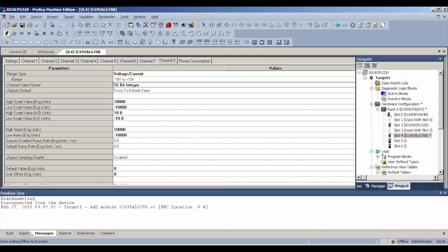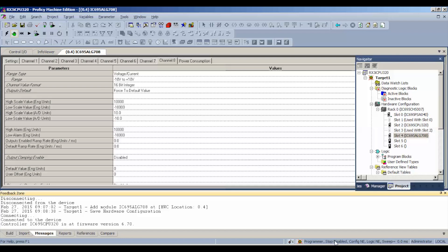Now that that's done I'm going to connect up to the processor. Click the hand print and the hand print toggles us to programmer mode. Stop disabled which refers to the inputs and outputs are stopped. Configuration and logic are not equal yet. That's important because the processor was doing something different before we gave it this particular device.